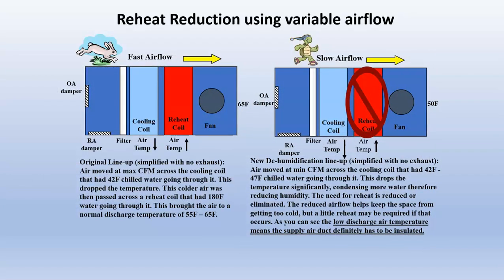So here's a slide about reheat reduction using variable airflow. Basically, the reheat is running here to get rid of humidity. So if you look at the original lineup, I've got fast air. See the bunny rabbit? I got fast air coming in. Let's see if I can get my pointer up there. I got fast air coming in. Temperature's dropping across the cooling coil, and then I'm heating it back up, and I'm putting out 65-degree air. This is getting rid of the humidity.